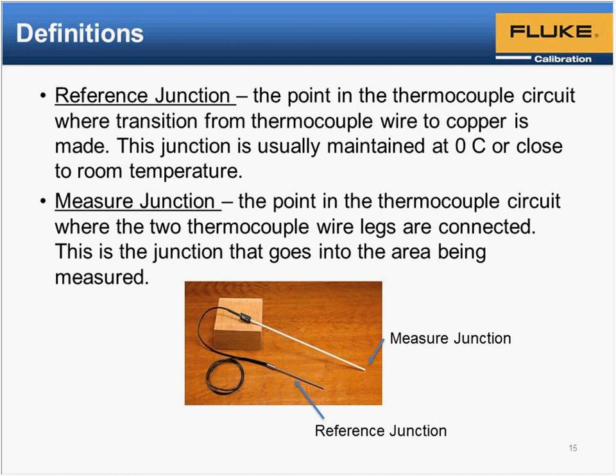But yes, I think that's a correct statement: for the ice bath, if you have better uniformity and smaller temperature gradients, then we get better results. Now, possibly related to this also is if you can make a measurement in a scenario where the temperature you're measuring is uniform, and then there's a very sharp transition from that temperature to room temperature, it provides a method where you could insert the wire at different depths and do a wire inhomogeneity test. If the gradient is spread out over a large area, it becomes a little harder.